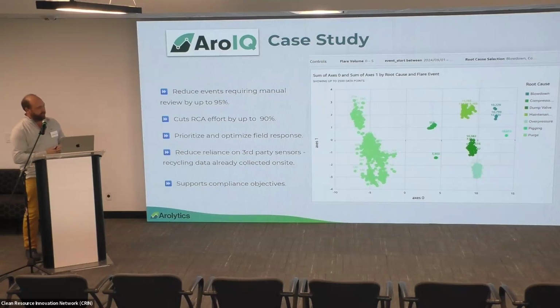In this example, this is six months of a client's data for every flare event that happened. Those dots could have been a second long, an hour long, or a day long, but we group them into like-caused events. The axes don't mean anything—they're 292 SCADA tags that were evaluated, condensed into an X and a Y.